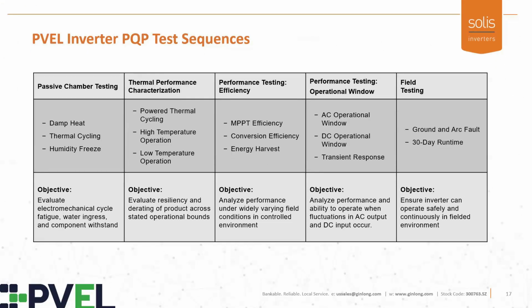So what are these product qualification program test sequences? What I've provided here is a high-level snapshot of different categories that the products will go through. Passive chamber testing is unpowered exposure to different environmental conditions. Prior to units going into any of these passive chamber tests, they get pre-characterized electrically, and then we put them in the stress, damp heat, thermal cycling, humidity freeze as listed here. Then we post-characterize the inverter products, and compare the pre and post-test electrical data to understand if things are beginning to degrade or fail as a function of that exposure.